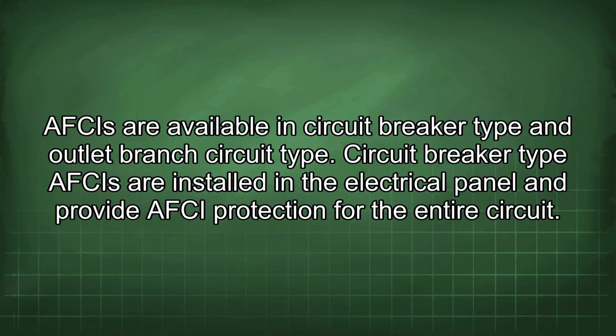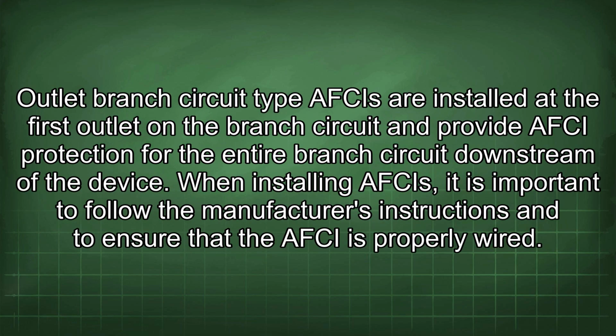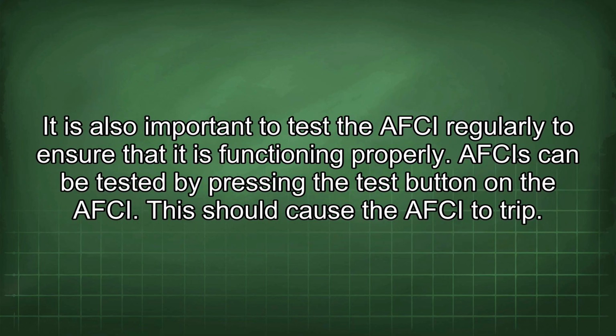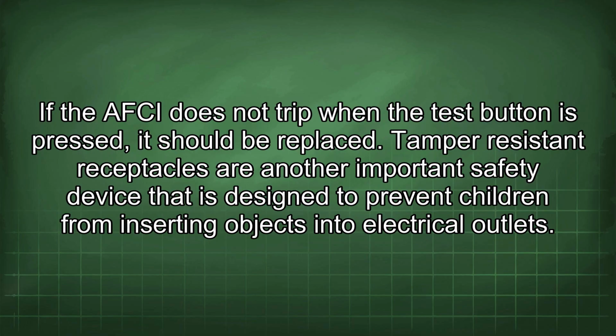Circuit breaker type AFCIs are installed in the electrical panel and provide AFCI protection for the entire circuit. Outlet branch circuit type AFCIs are installed at the first outlet in the branch circuit and provide AFCI protection for the entire branch circuit downstream of the device. When installing AFCIs, it is important to follow the manufacturer's instructions and to ensure that the AFCI is properly wired. It is also important to test the AFCI regularly to ensure that it is functioning properly. AFCIs can be tested by pressing the test button on the AFCI. This should cause the AFCI to trip. If the AFCI does not trip when the test button is pressed, it should be replaced.